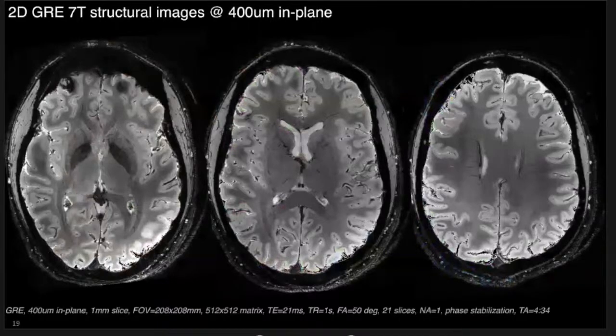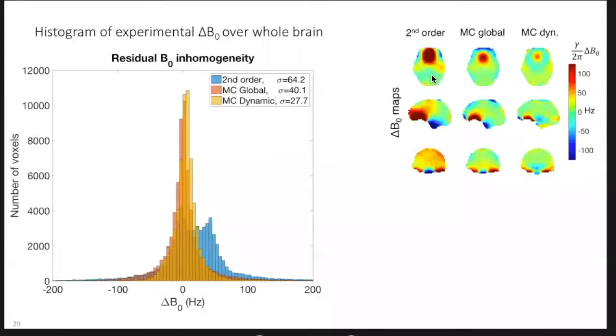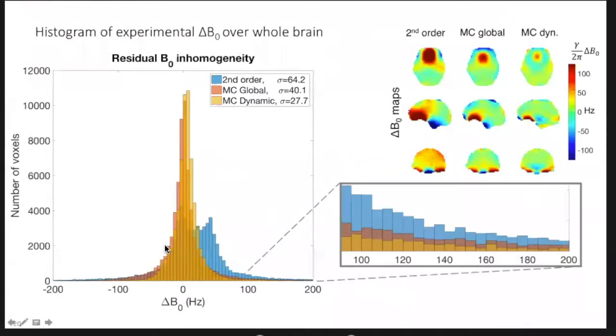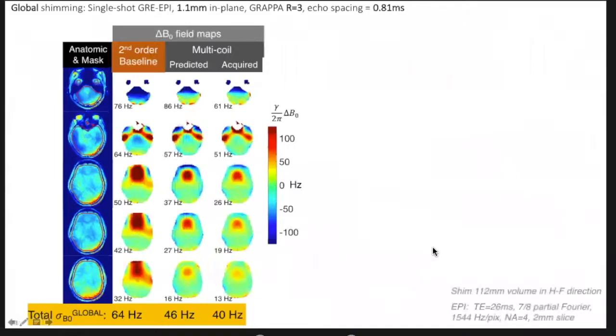So the RF coil works well. How about the shimming? This is a comparison of the field maps with the second-order shim, a global multi-coil shim where you shim the whole head at once, and a dynamic shim where you step through the slices and you update the shims for each slice, which you can't do on conventional scanner shims because they can't switch quickly. And you can see that the field map is not perfect, but it's a lot better than it was with second-order shims. And you look at the histogram of the B0, it especially gets good out in the tails where you're getting the worst geometric distortion in EPI, which is confounding the analysis.